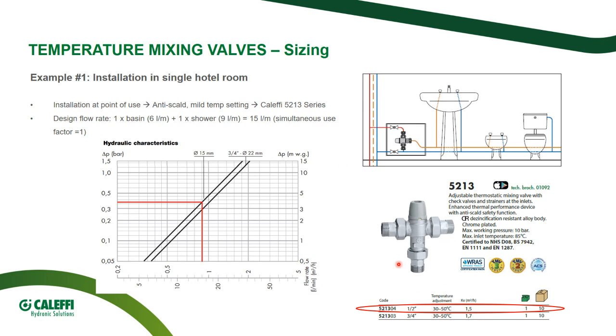So I will take the Caleffi 5213 technical data sheet. I will take the hydraulic characteristic chart, and I will enter with my design flow, that is 15 liters per minute. If I identify the M15, so 1/2 inch valve size, my pressure drop is around 0.4 bar, so 4 meter water gauge. That is very, very nice. So the proper size for this application will be 1/2 inch.